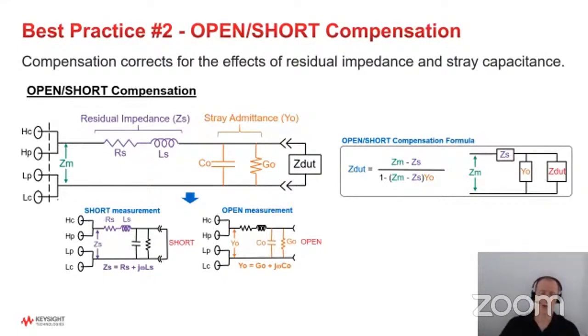You're going to do the open. You just make sure that there's no DUT connected there, and you lift it up or just disconnect the cables, and you run the open compensation routine, and it'll do the open compensation. And then you short those two cables together with a wire or some other means, and you run the short compensation, and that will actually eliminate a lot of the residual impedance and capacitance effects on the cables. So that'll give you pretty good results in general. A lot of times that's all you need to do.